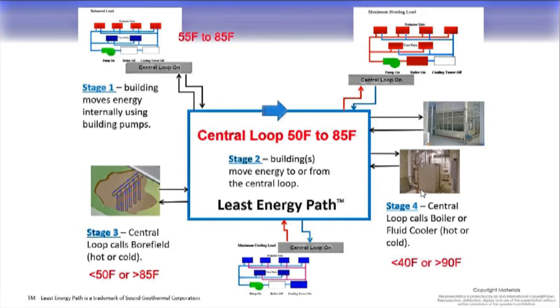When we come back in, we put it together, we started running, and bingo, here we go. Now I can get some pumps down. So it's not unusual for me to take a 50 horsepower pump and see it working on a system hour after hour at 20 hertz, or slightly under depending on the size of the pump, while pushing maybe 1,000 tons.